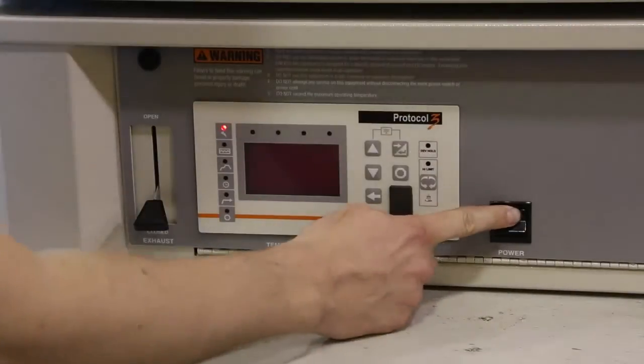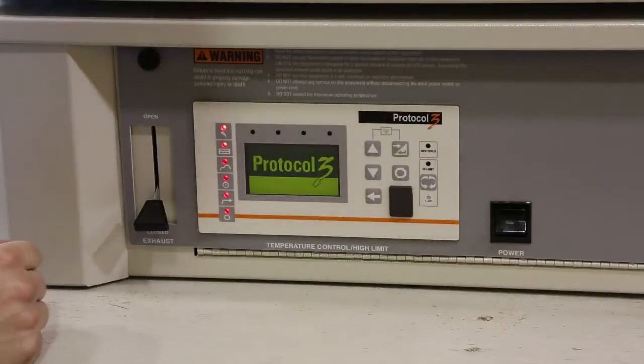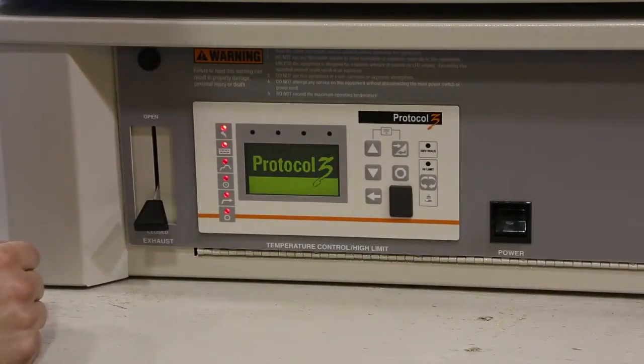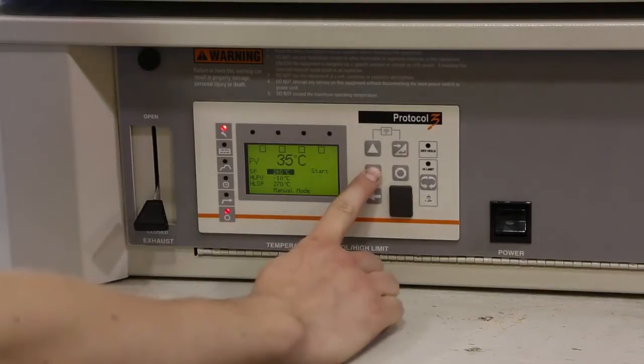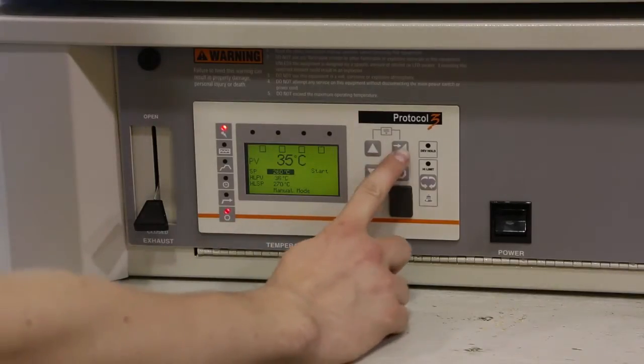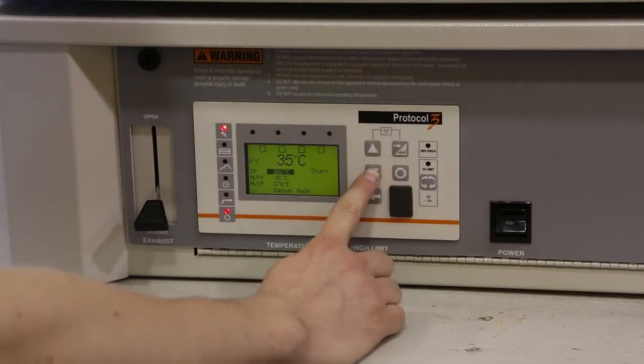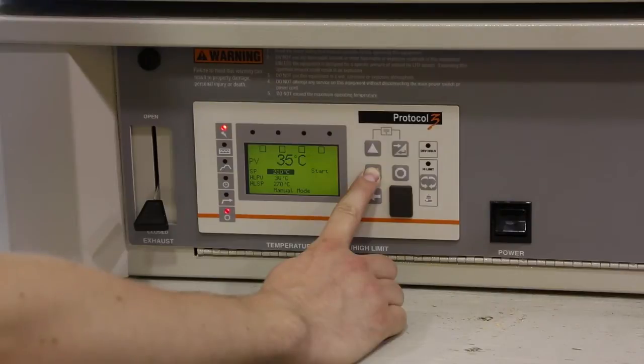Once the thermocouples are all placed and connected, set the oven to the temperature to be used in the process. The oven should then be allowed to stabilize for a minimum of 30 minutes before measuring.